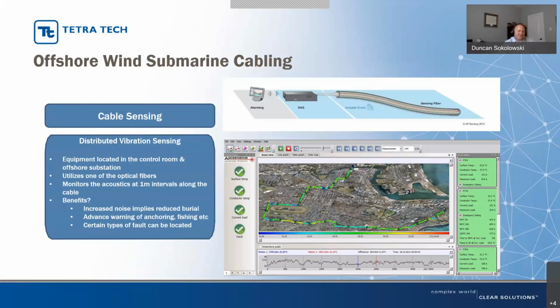It can also be used for some types of cable faults, such as partial discharge, which can be very difficult to locate with traditional techniques. Partial discharge is basically a partial breakdown of the insulation, creating a ground fault and a spike in noise. These systems can detect that and give a hint about fault location if the worst happens.